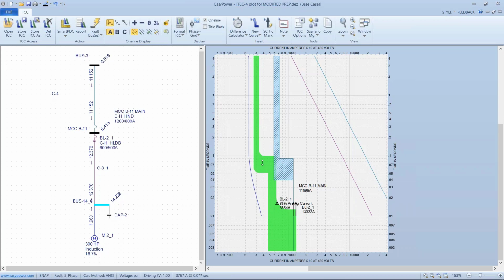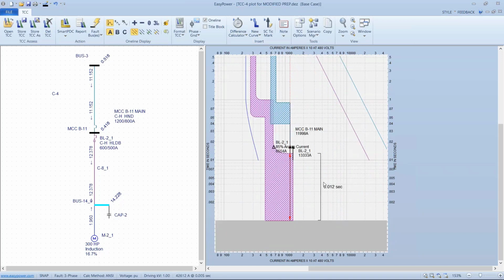Now to verify that I have time difference between them, I'll pick out two curves and use the difference calculator. And here at the maximum current, I see a separation of 12 milliseconds. If I slide it over to the arcing current, I see 23 milliseconds between the time this first device clears and the next device will start to sense the fault.